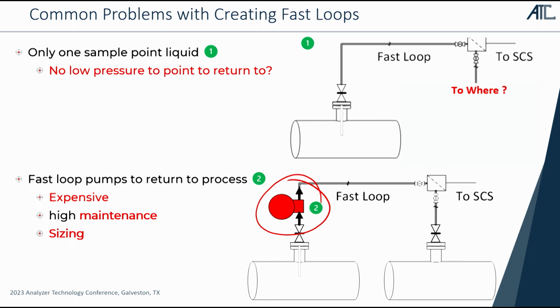We had a meeting this week talking to some people, and they said the problem was they oversized the pump, and it was cavitating on the inlet side. And so who's going to do the sizing for the pump? Did it get sized properly for my application? And then we also say, well, it becomes this little bit of an engineering avalanche.